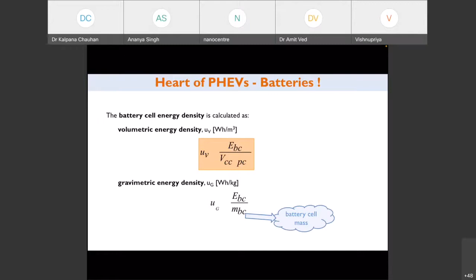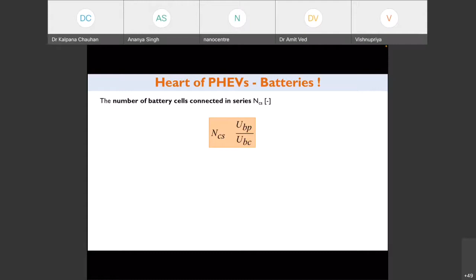The arrangement of these cells: we consider that the battery pack is made up of several strings, connected in parallel. The number of battery cells connected in series, NCS, in a string is calculated by dividing the nominal battery pack voltage, UBP, by the voltage of each battery cell, UBC. The number of strings must be an integer, so the result of calculation is rounded to the higher integer.